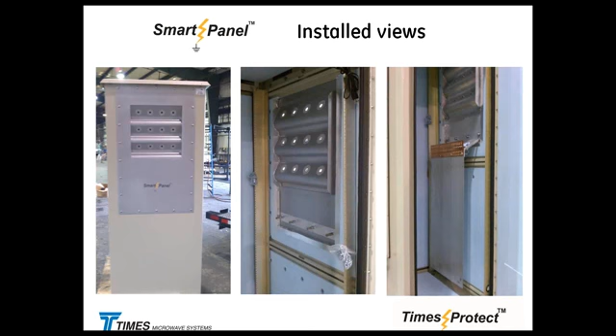Here's a good example—a guy called me. He had a water tank with some antennas mounted, using LMR 600 cable. He was from North Carolina and said every time he had a lightning storm he kept losing his channel banks. He sent me this picture—a couple of LMR 600 cables coming here, protectors installed, and jumpers. But the protectors weren't grounded at all. They were sitting there very happy, not being bothered by anything, and the guy kept blowing his channel bank.